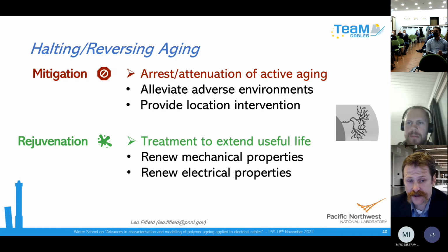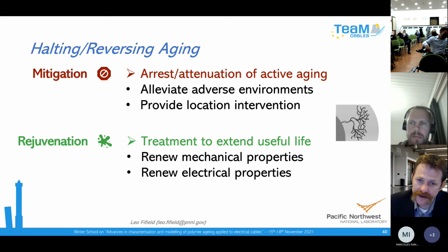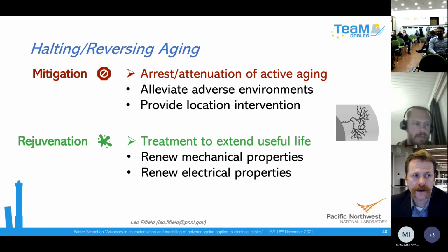We've had some initial efforts in the past to look at rejuvenation techniques to try to recover property loss due to thermal aging. For instance, if there's been bond scission and breaking of polymer chains in the material, introducing a chemistry that can soak in and cross-link might recover some of those properties. Another degradation mechanism, for PVC, is plasticizer leaking out of the material, which often leads to property degradation—so you can rejuvenate that by imbibing plasticizer back into the material. Those are some of the thoughts related to rejuvenation: trying to recover lost properties.